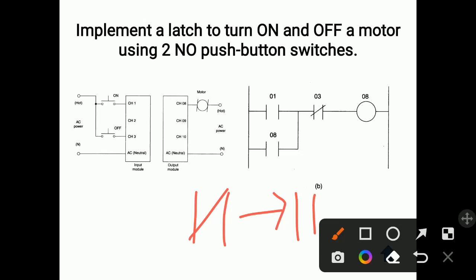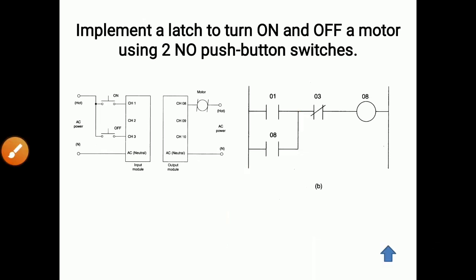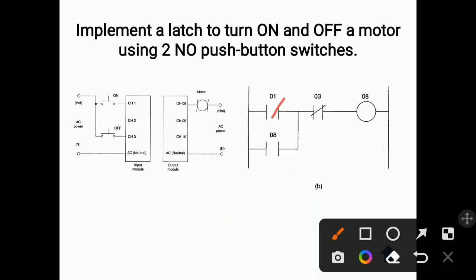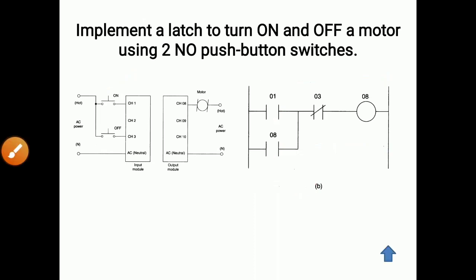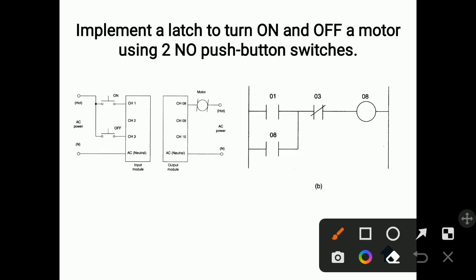If we want to keep the motor continuously on for some time period, we have to use latching. When you close this contact, the coil gets energized and at the same time this zero eight switch also gets closed — because both zero eight contacts are similar — so the supply can continue through the latch path. Even if you remove your hand from push button one, the current can flow continuously and the motor remains on.